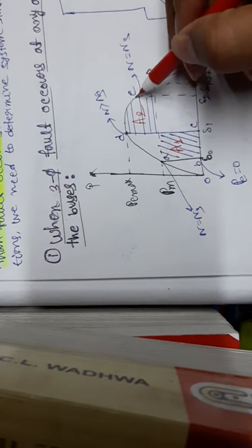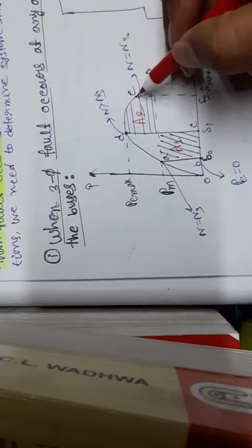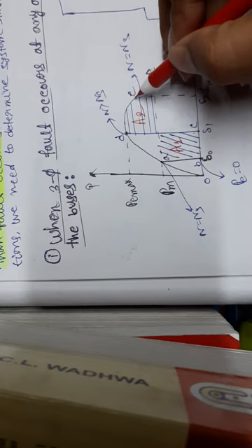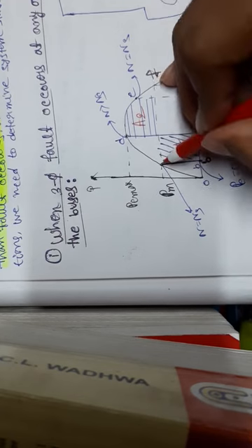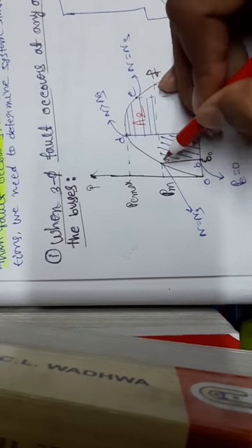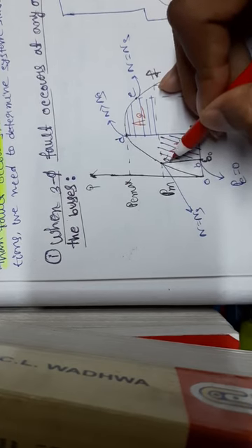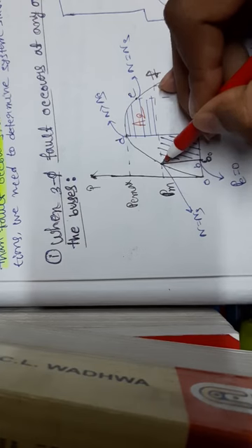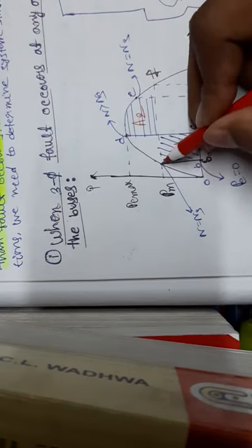When it reaches point C, at that point the acceleration energy will be exhausted. Now it will start to decelerate like that, and it will come to point A, and at point A it will oscillate for a while. Then it will again come back to its normal operating point. It is a stable point where PM equals PE.